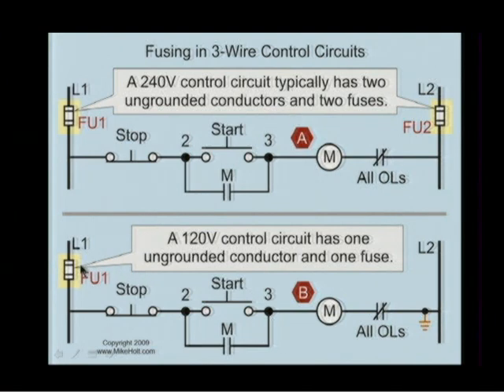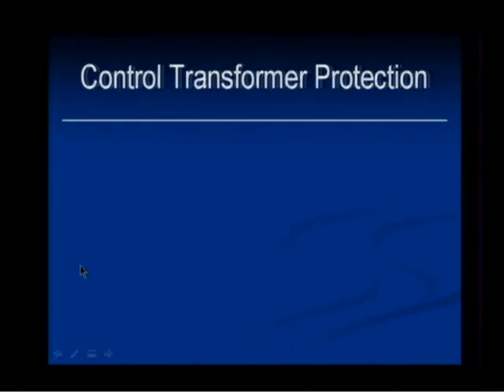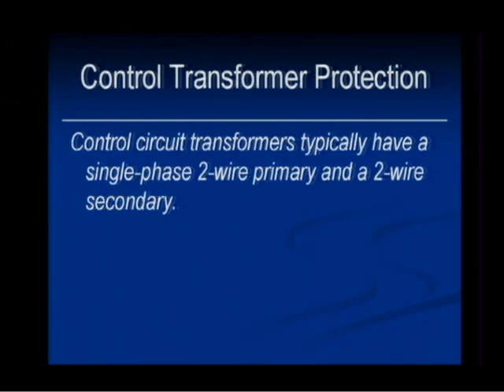And if it's a 120 volt circuit, we just fuse one phase. Control transformer protection. Now, this is where you have a lot of transformers. Now, let's talk about that. Control circuit transformers typically have a single phase, 2-wire primary, and a 2-wire secondary.